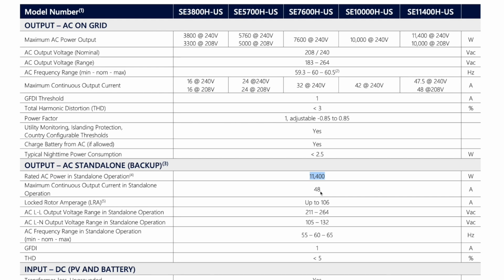What this means is regardless of the size of the Energy Hub inverter, if it is a domestic inverter, you must size the wire between the inverter and the backup interface to number 6, and the breaker in the backup interface must be 63 amps. Again, the reason is that even if that 3800 watt inverter only has 16 amps when connected to the grid, as soon as it goes off grid and it discharges through the backup interface to the critical loads panel, it can discharge up to 48 amps continuous. And so that'll require number 6 and a 63 amp breaker.